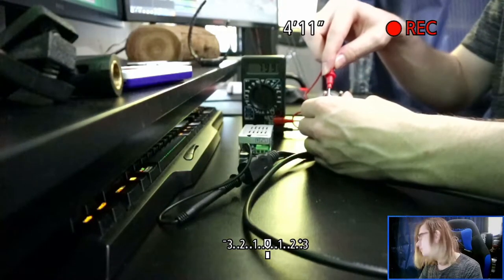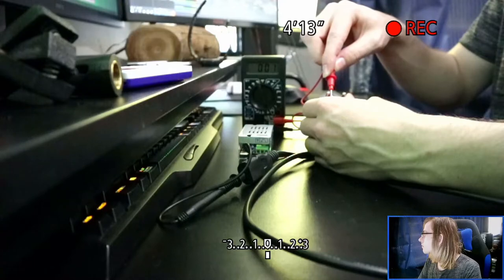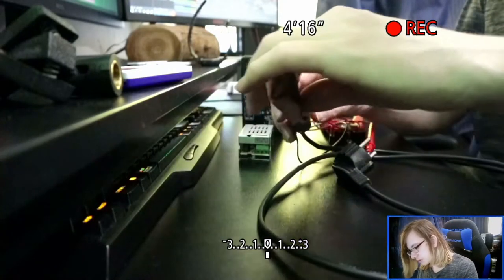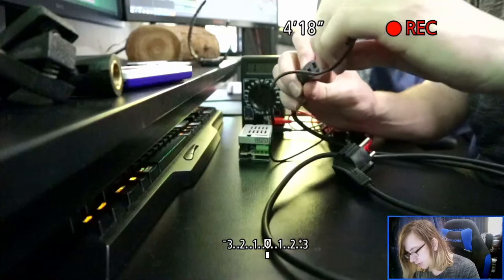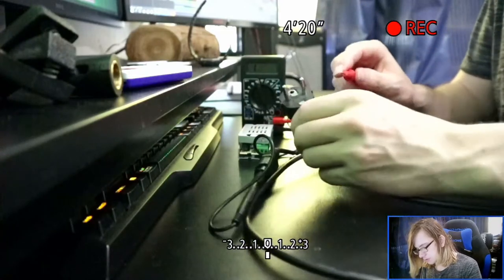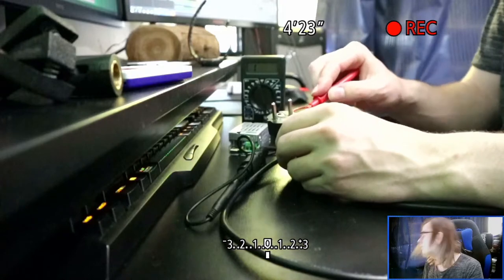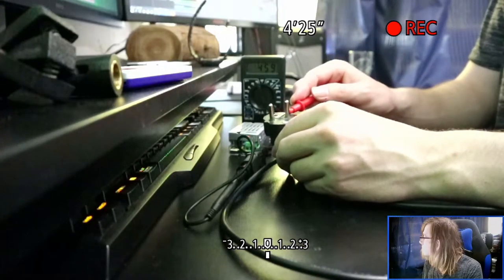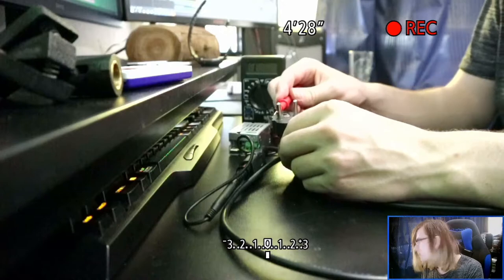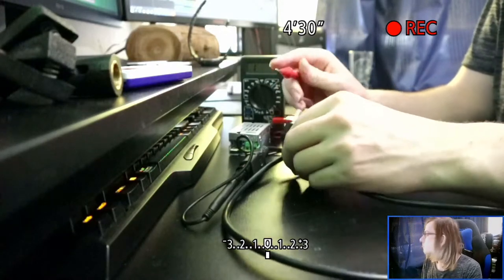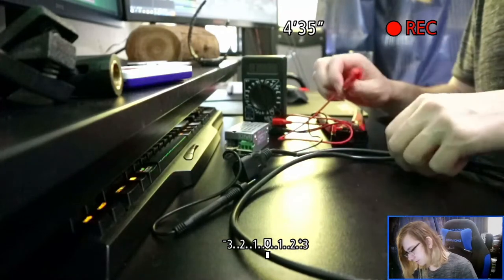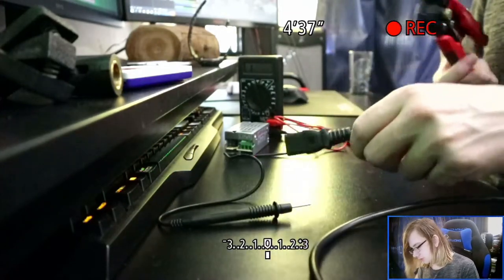If I were to touch this, if I now were to touch the middle one over here you see the value goes to zero. If I were to put this into the live side and touch the pin I scratched underneath to mark that that's live, we'll get the same result. If I were to touch anything else it will stay to one because these wires are all completely isolated. So that leaves this to be neutral.